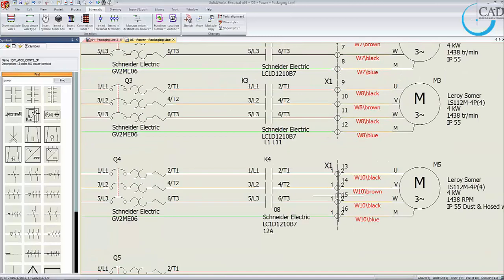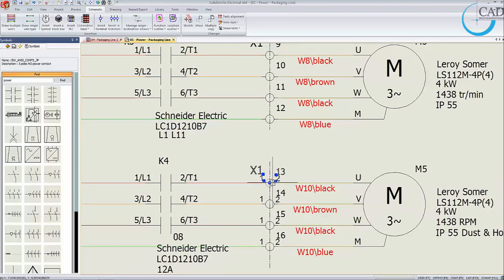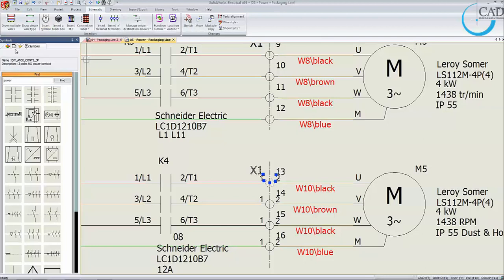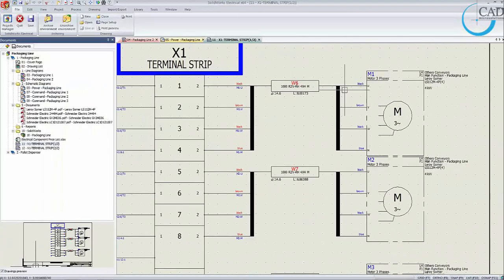Now, the conventional way to create a terminal strip drawing of X1 after doing the electrical design would be to manually write down the from-to list. In SOLIDWORKS Electrical, you can automate this process with a single click — simply right-click and select 'Draw X1 terminal strip.' If you go to the sheet, the terminal strip drawing is created right away based on the schematic logical connections.